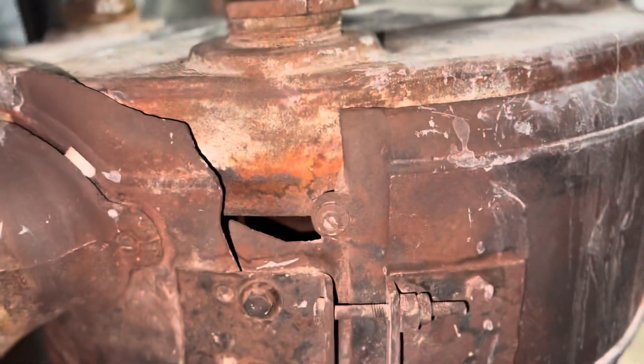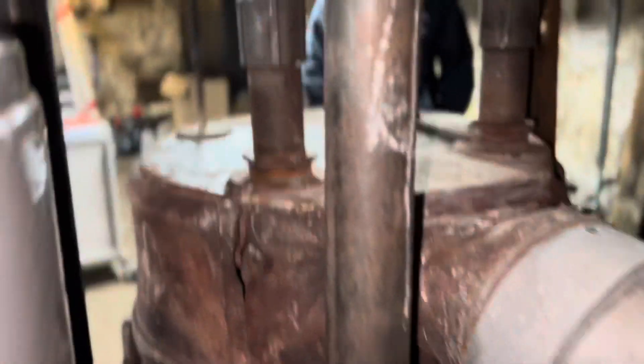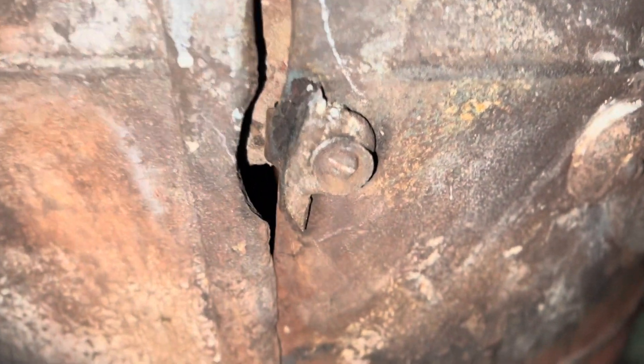Here's a good view of one of the spots that blew apart — right through to the fire chamber. Big blowout in the back right here. That's the water line, don't bend that. Another big crack in the system right along here. Another blowout in the back. This house should have gone up in flames.